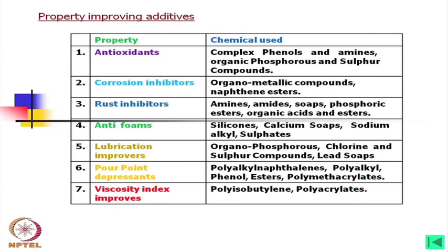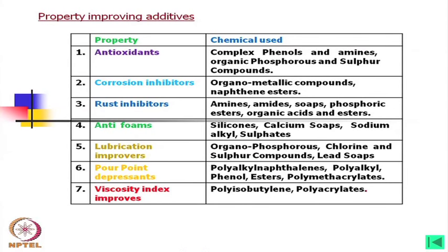The anti-foam additives include silicones, calcium soaps, sodium, alkyl and sulfates. Regarding foam: when any liquid is being discharged from a pump and put into a tank, you will find foam. As such that foam may not be that harmful, but with the foam, air bubbles go inside the oil and that creates a problem. So it is better there should not be much foam. This can be controlled externally using baffles and separators inside the tank, but chemical compounds will help in a better way.